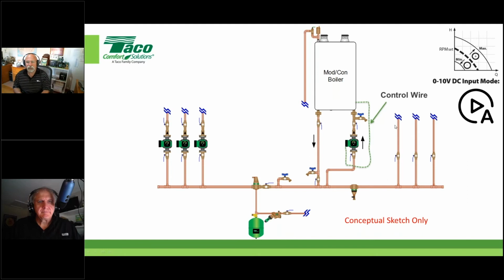The first thing I'm going to say is if we have the capability of letting the boiler manufacturer control our pump, then we want to let that happen for a couple of reasons. Just understand what this picture is showing you. I have a ModCon boiler, depicted as a wall hung unit. This circulator will have line voltage coming from the same boiler, but it also has a control wire that allows the actual boiler manufacturer to control the speed of that circulator based on some information.